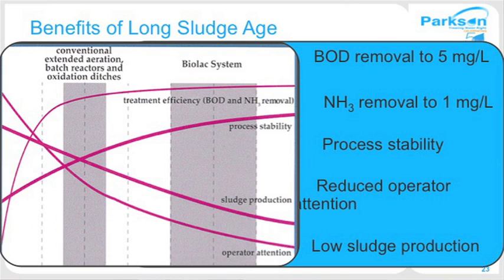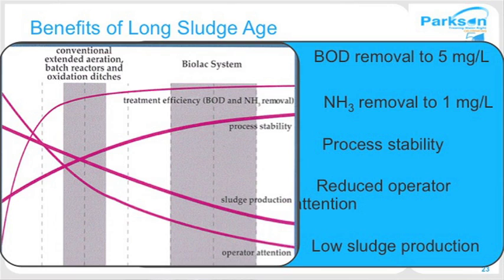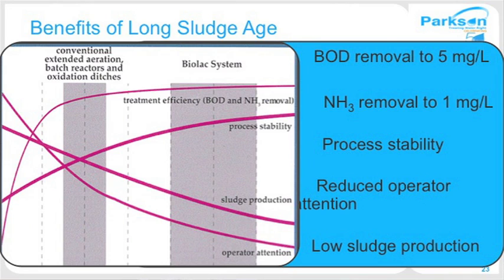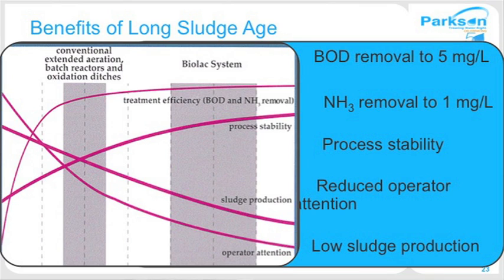The benefits of the BioLac process design stem from its long sludge age of 30 to 70 days compared to conventional systems at 15 to 30 days. With extended sludge age, you get minimized sludge production, reducing the cost to further treat and stabilize sludge. The process is much more stable and consistent in effluent quality even in cold climates, and requires minimum operator attention. A lot of BioLac installations are in small municipalities where the operator has other duties — so it's really a peace-of-mind, simple operation.